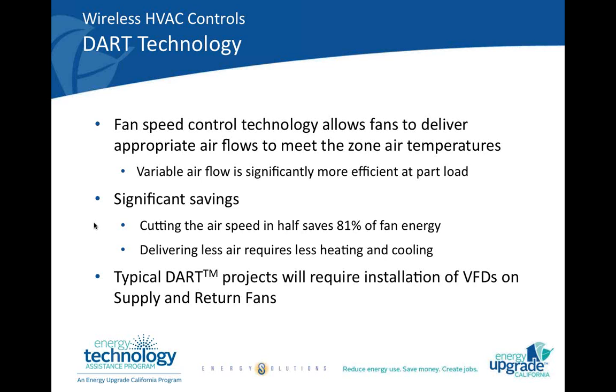Furthermore, delivering less air requires less heating and cooling of the supplied air, so you can get heating and cooling savings as well. One thing to note is that a DART project will require installation of VFDs on your supply and return fans if they aren't already installed. Next slide, please.